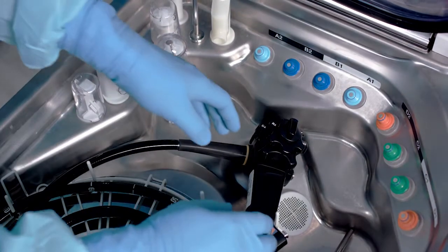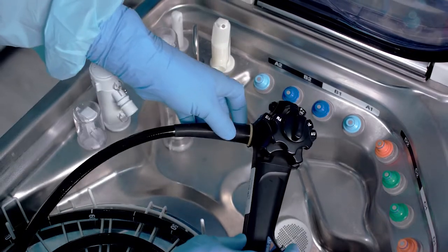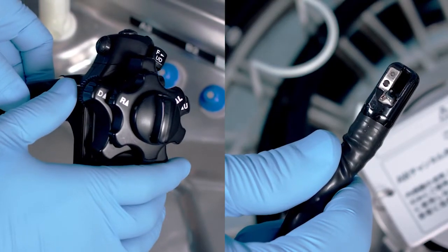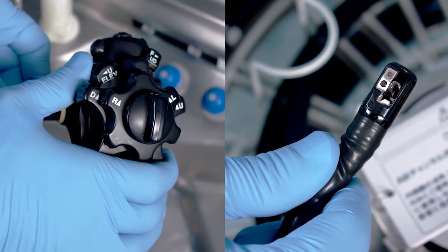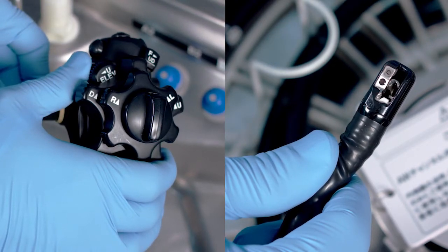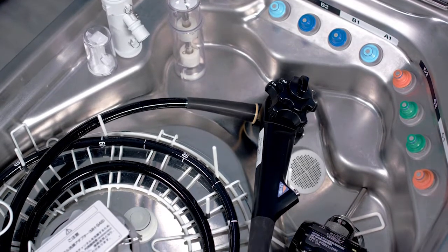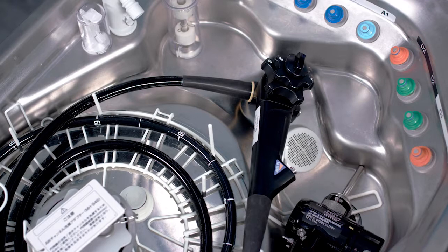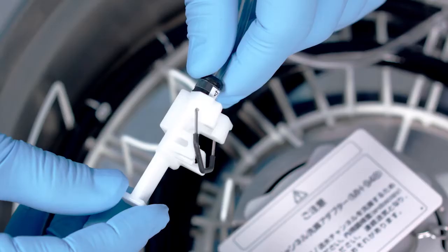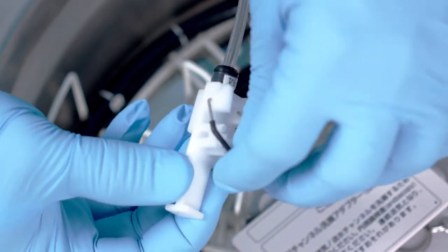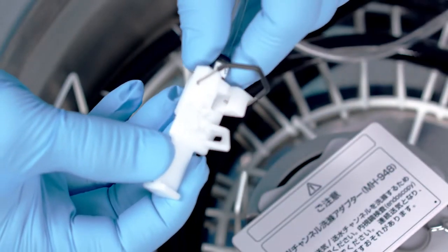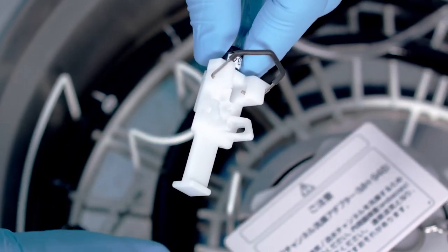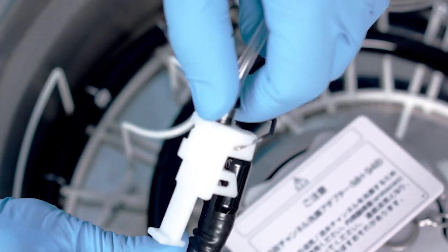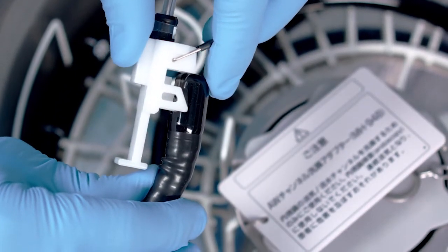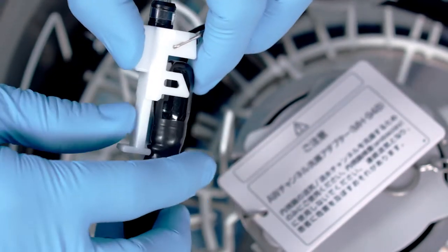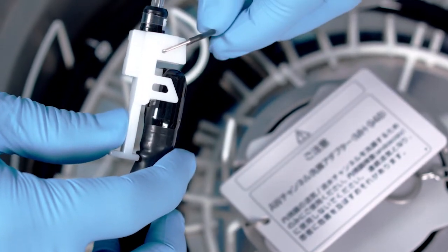To begin, turn the elevator control lever, labeled U ELEV, on the endoscope's control body in a clockwise direction. Do this until the forceps elevator stops. Failure to do this prior to connecting the MAJ2330 connecting tube can result in insufficient elevator reprocessing. Next, raise the connecting lever of the MAJ2330. Insert the endoscope distal end by aligning the nozzle of the endoscope side connector into the instrument channel outlet of the endoscope. Then, lower the connecting lever to secure the distal end of the insertion tube.